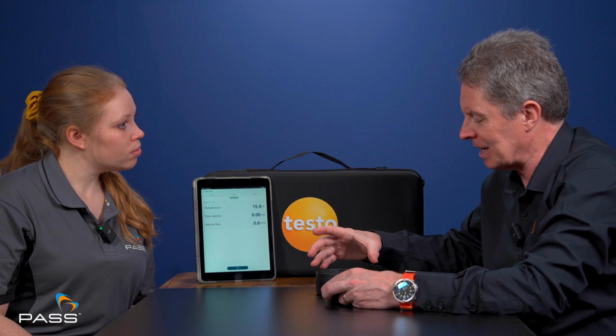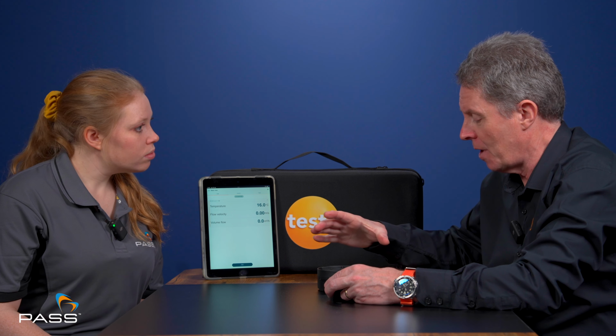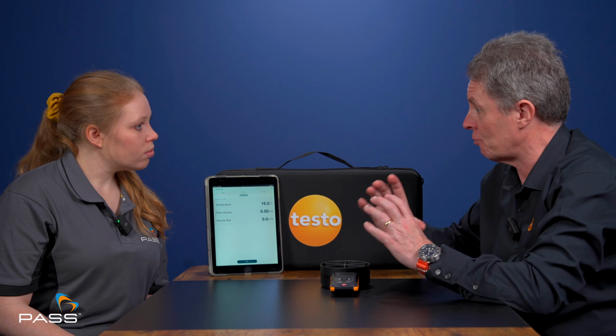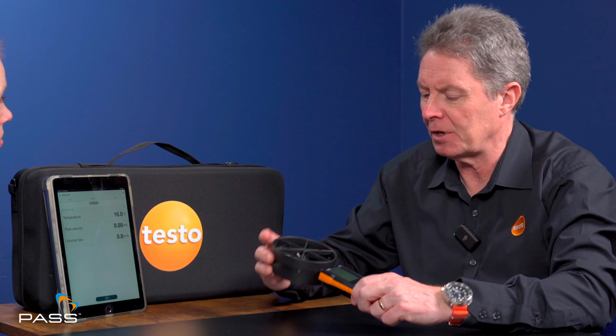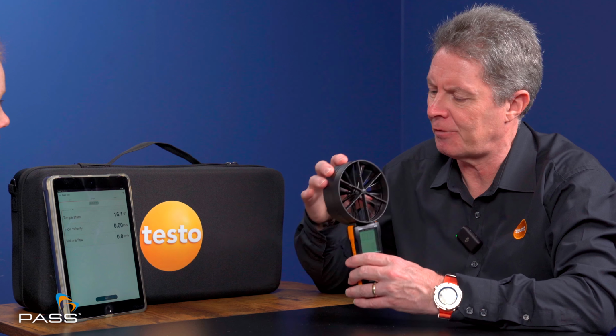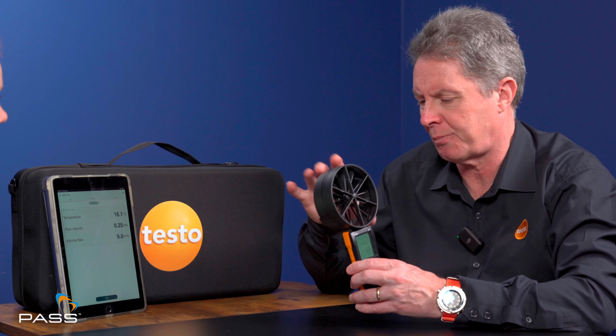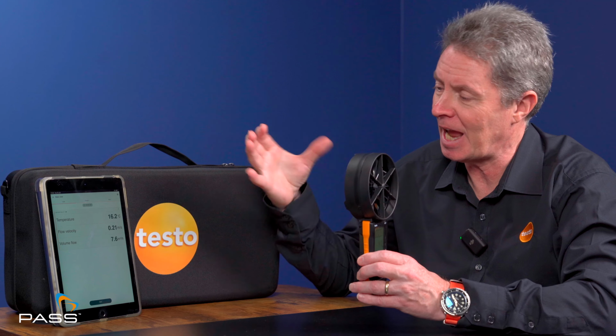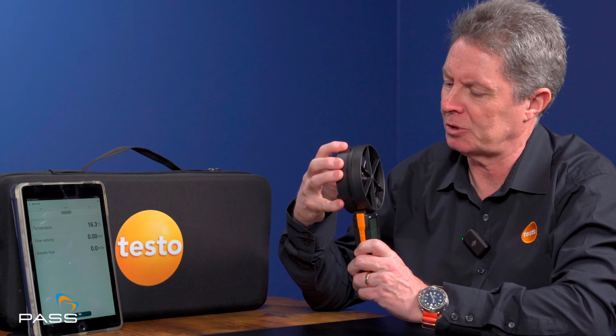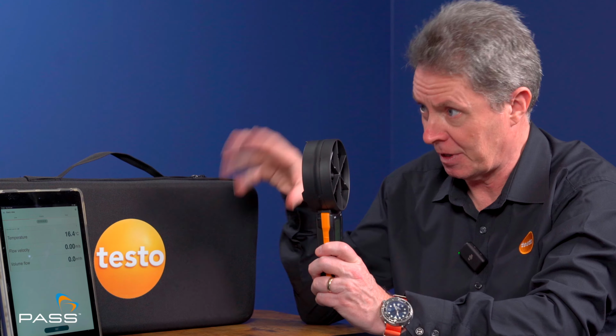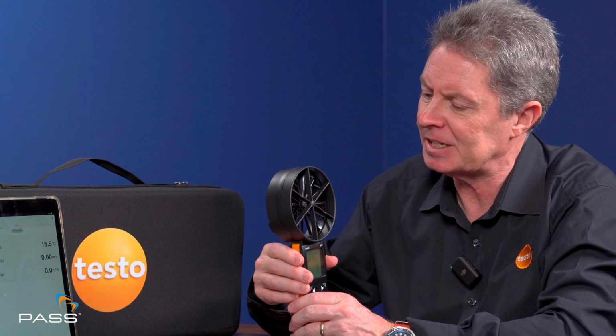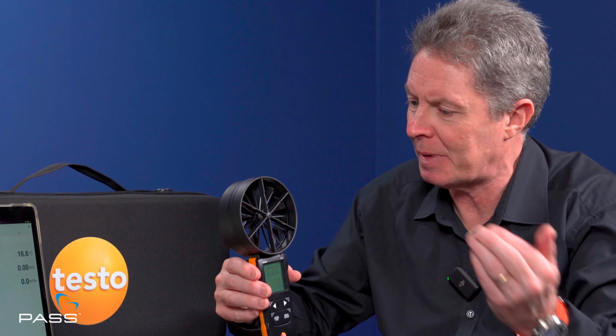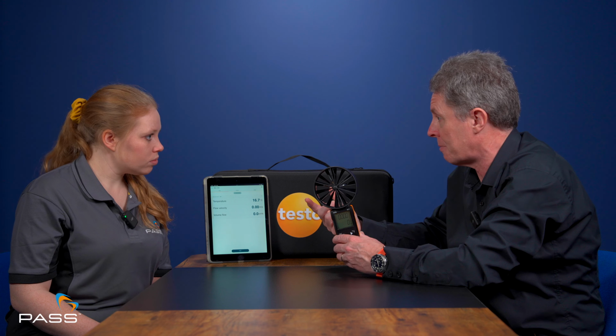So the 417 is a tool that can be used for measuring airflow, typically at a vent or a grill. Normally you use this device with what's known as a set of hoods, which come as part of the kit, and the hood is capturing the air. So the hood clips onto here. You put the 417 up against the outlet, and what you're measuring then, if it's an extract air, is the air being extracted from the room through the anemometer and through the grill. If it's supply air, i.e. fresh air coming in, it would be coming the other way, but the anemometer can read both directions.